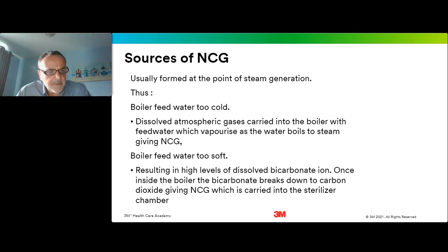The other problem is that the feed water might be too soft. And if people are using water softeners rather than RO or deionization systems for their boiler feed water, then as the bicarbonate, which is created during the softening process, breaks down to carbon dioxide, it will, of course, be carried over in the steam as a non-condensable gas.